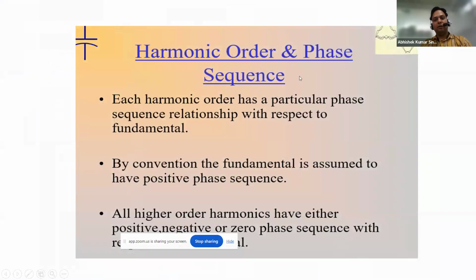Now, harmonic order and phase sequence, as we already discussed. The harmonic order has a particular phase sequence relationship with respect to the fundamental, because when we are discussing something, it should always have a reference. The reference is the fundamental, that is the 50 hertz. That's why we are saying third harmonic. What is the third harmonic? 50 multiplied by 3 is equal to 150. So the reference point is the 50 hertz.